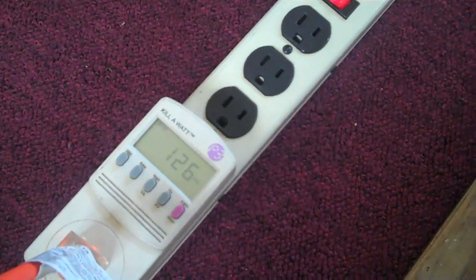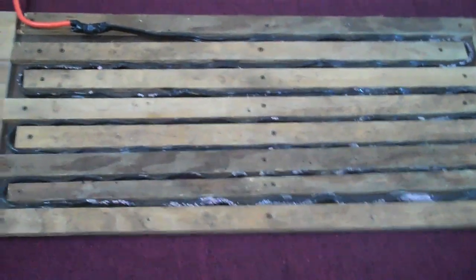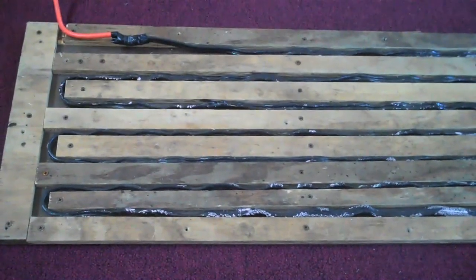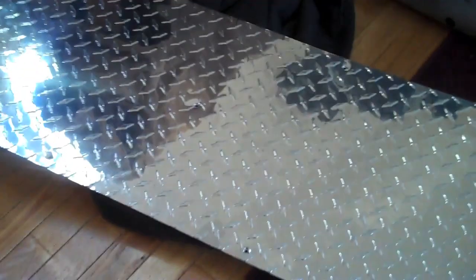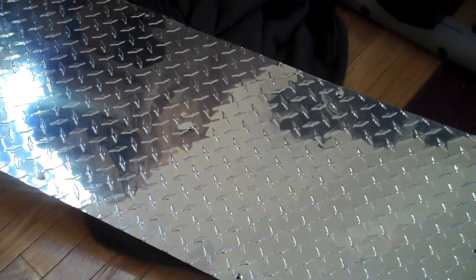the watts to come up here and we're pulling about 130 watts right now. So that's 130 watts of heat out of a panel that's basically three feet wide and 18 inches across the other dimension.